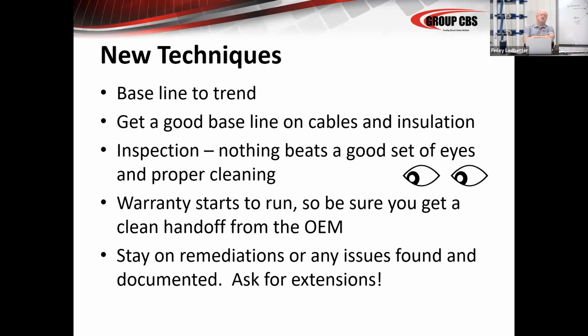You see a lot of stuff that comes out of the manufacturer's plants that may have sat on the plant floor in the last few years. It may have sat there a year, it may have sat there 2 years, because the construction cycles were so long. A lot of this equipment sat on the plant floors a long time. Make sure it's visually inspected. That's just as important or more important than the electrical tests.